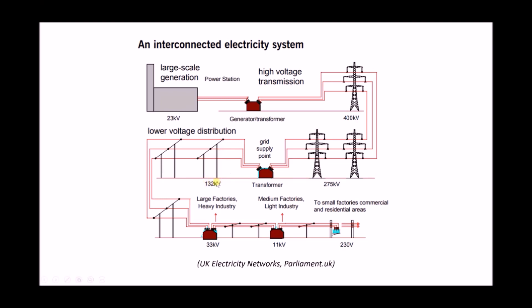132 kilovolts is still too high for delivering electricity to factories and residential premises, so we need to step that voltage down further. Typically the voltages supplied to large factories and heavy industry is 33 kilovolts. For medium factories and light industry we have voltages of around 11 kilovolts, and for residential properties we step that down again to 230 volts. So the standard mains supply in domestic properties is 230 volts, 11 kilovolts for small factories, and 33 kilovolts for large factories. That gives us our full network: generation, transmission, distribution, and supply.